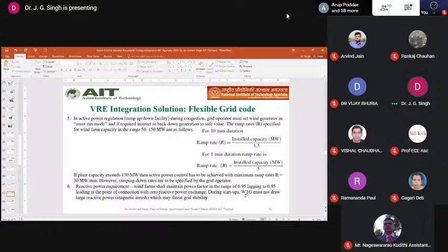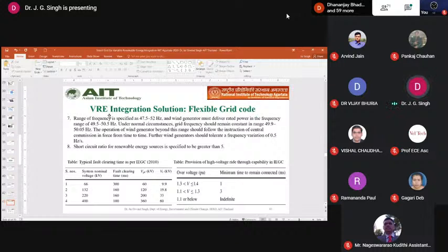Reactive power should also range from 0.95 lagging to 0.95 leading at the PCC. During startup of wind turbine generators, they must not draw large reactive current, especially magnetization current, which will create stability issues. And this is the voltage range. Operation of wind generators beyond this range should follow the instructions of the central commission enforced from time to time. Further, wind generators should be able to tolerate a frequency variation of 0.5 hertz per second. And also SCR for renewable energy sources is specified to be greater than 5.